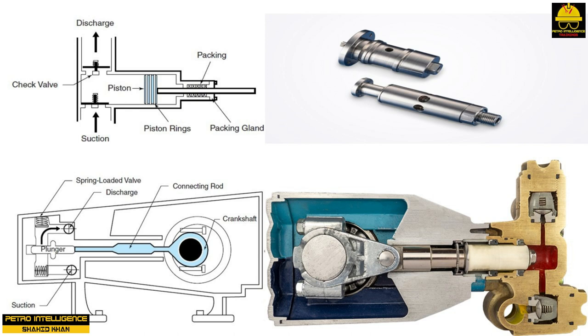This type of pump continues to operate no matter how high the discharge head is. The typical piston pump has a piston, piston ring, connecting rod, suction and discharge valves, casing and cylinder, and relief valve. Piston pumps are sealed internally and externally. Internally, the piston rings form a seal on the piston that can be seen only by tearing down the pump. The external packing seal is located where the piston rod enters the casing. Reciprocating plunger pumps, as shown in picture, operate with a back and forth motion and a device called a plunger to displace controlled amounts of liquid.